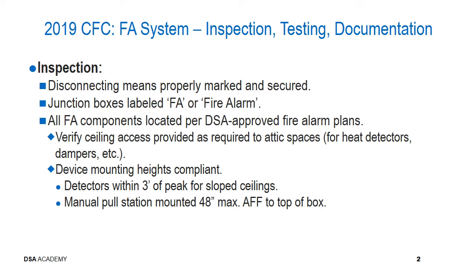Ensure that device mounting heights are compliant. Remember, for peaked or sloped ceilings, a detector must be within 3 feet of the peak. Manual pull stations, when provided, must be mounted 48 inches maximum above the finished floor as measured to the top of the box.